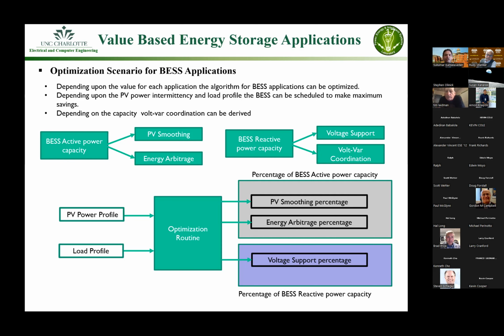However, you want to make sure that the capacity is sized properly, so that the total MVA rating of that inverter has enough reactive power for what is needed at that specific location. I don't know whether you are familiar with that, so I just wanted to mention it to you. The reactive power coming from the battery energy storage system can obviously be utilized for two purposes. One is voltage support, another is volt-var coordination.